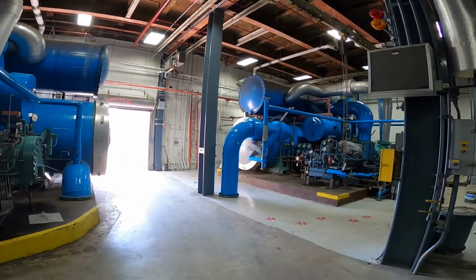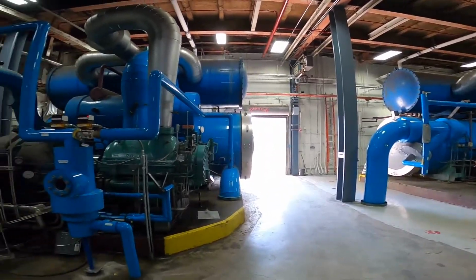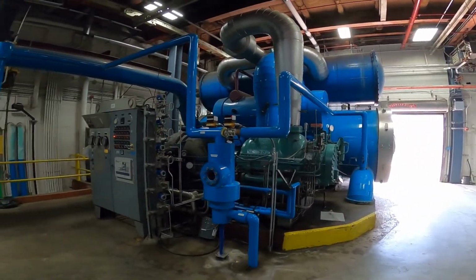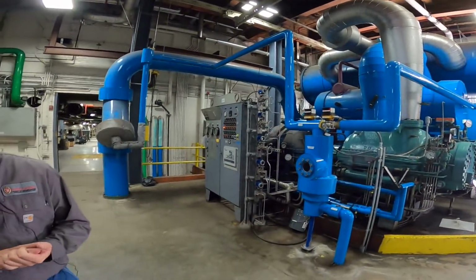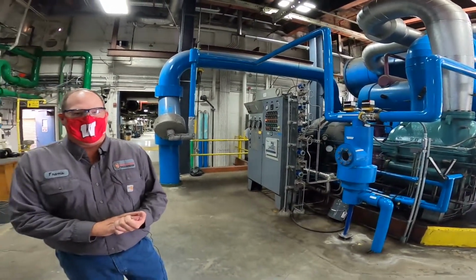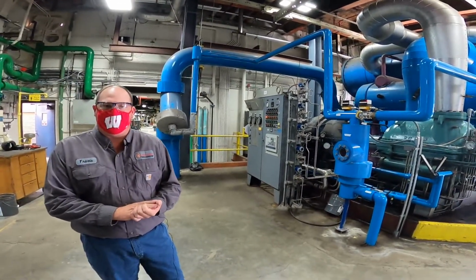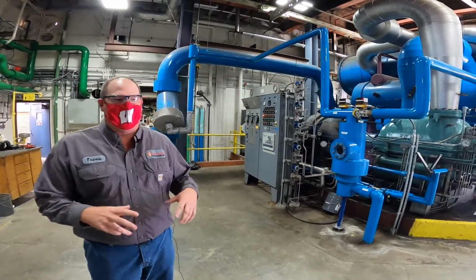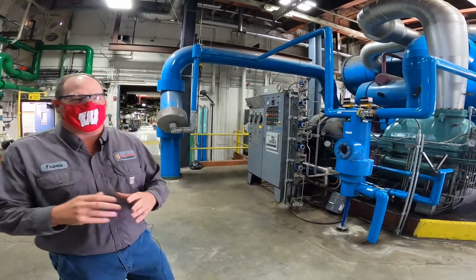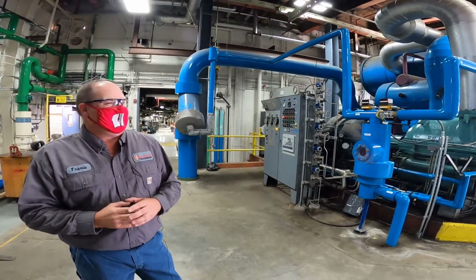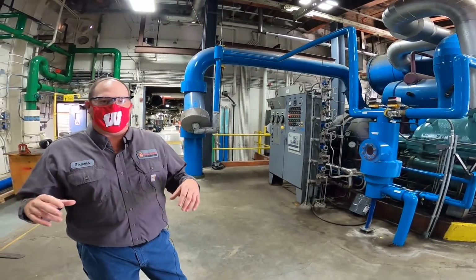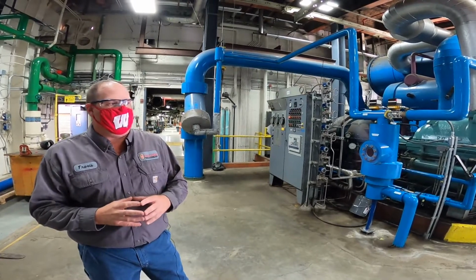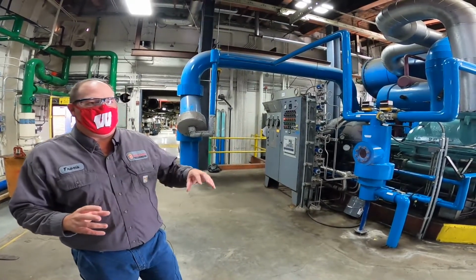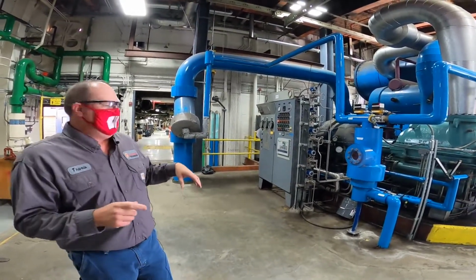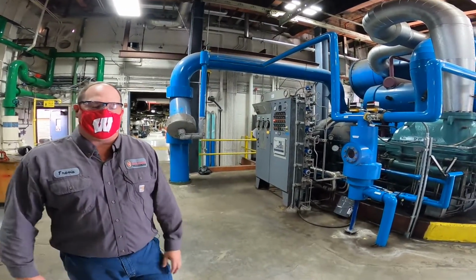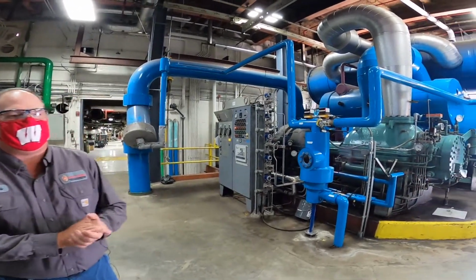So we're heating and cooling the entire campus, 3 hospitals, and when everybody's on site, students, faculty, staff, you're looking at a population anywhere from 60 to 70,000 people that we're heating and cooling centrally from this plant, as well as the 2 other ones on campus. So right here you're looking at 24,000 tons of cooling capacity, and again, they're all steam turbine driven, using 175 pounds of steam in this facility.